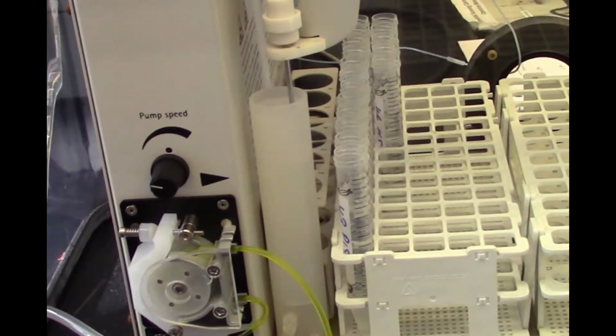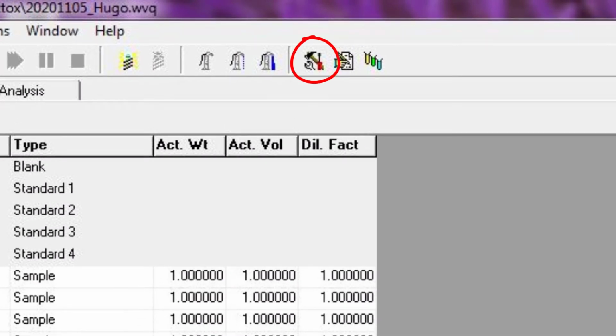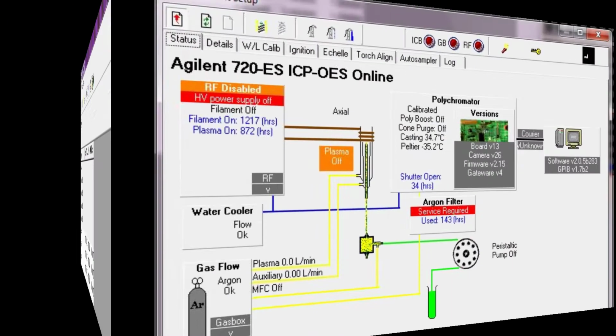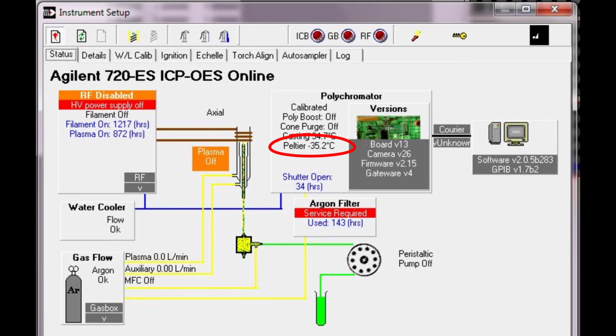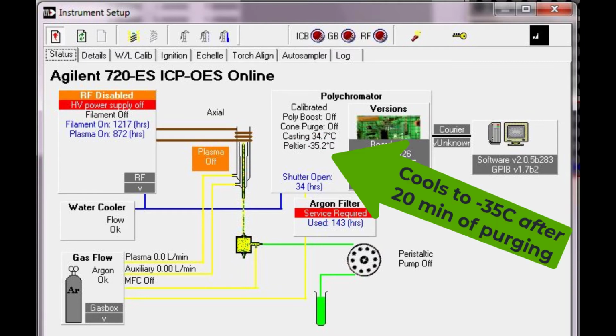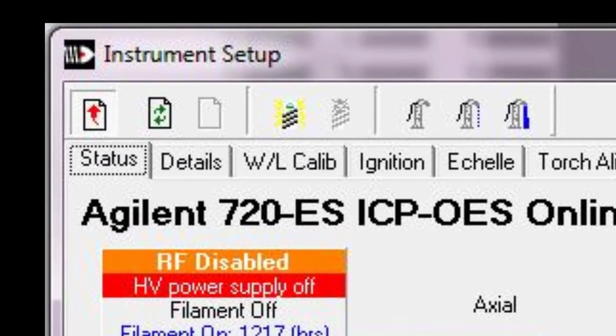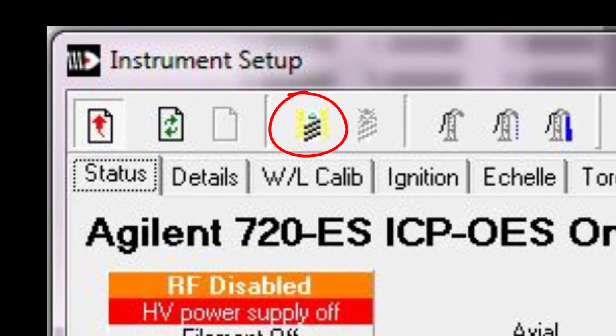Now, you're just about ready to start your run. Click on the hammer icon once more to enter the Instrument Setup window and look at the Peltier value. If it is still at room temperature, wait another 10 minutes before contacting a staff member for help. It's pretty common when you become more efficient at setting up the instrument to think that this number should have changed, but you haven't yet reached the required 20-minute timer from when you started the software. Once this value reaches -35 Celsius, click on the 3-lined image surrounded by yellow to turn on the torch.